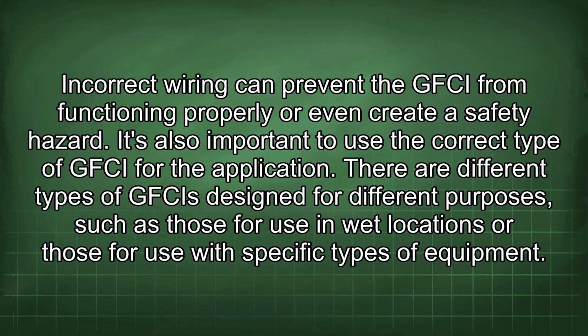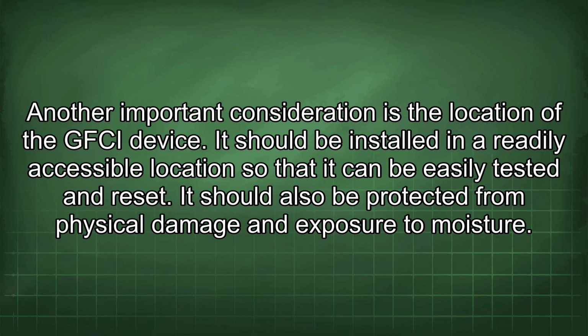It's also important to use the correct type of GFCI for the application. There are different types of GFCIs designed for different purposes, such as those for use in wet locations or those for use with specific types of equipment. Another important consideration is the location of the GFCI device. It should be installed in a readily accessible location so that it can be easily tested and reset. It should also be protected from physical damage and exposure to moisture.